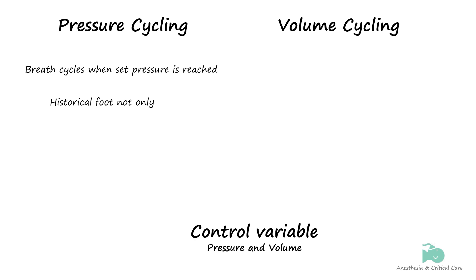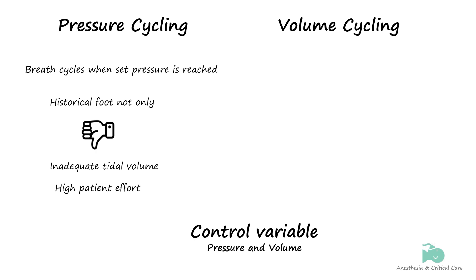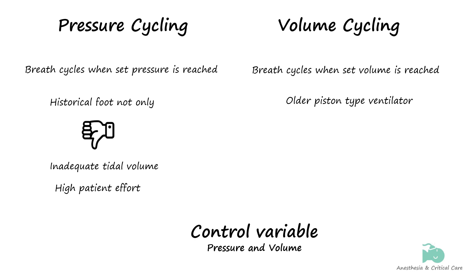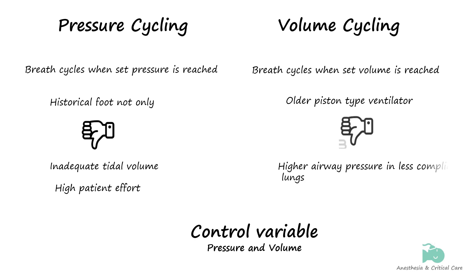Pressure cycling was famous in the past because it required nothing more than a spring-loaded diaphragm valve as the pressure cycling mechanism. It did have drawbacks, like inadequate tidal volume if the pressure threshold was set too low, and required higher patient effort to cycle the breath. Similarly, volume-cycled breaths end when the specified set volume has been delivered. Older piston ventilators were volume-cycled, delivering a predetermined volume before cycling to expiration. However, volume cycling has the propensity to generate high peak airway pressures when lung compliance deteriorates, resulting in large incidences of pneumothorax in the past.